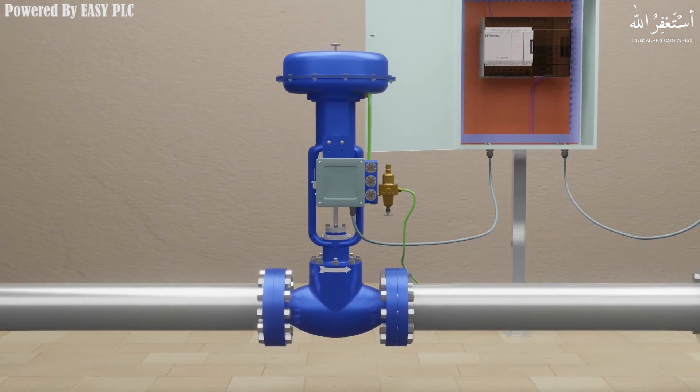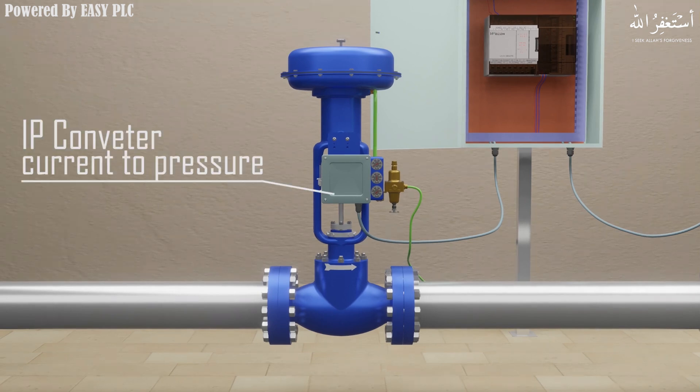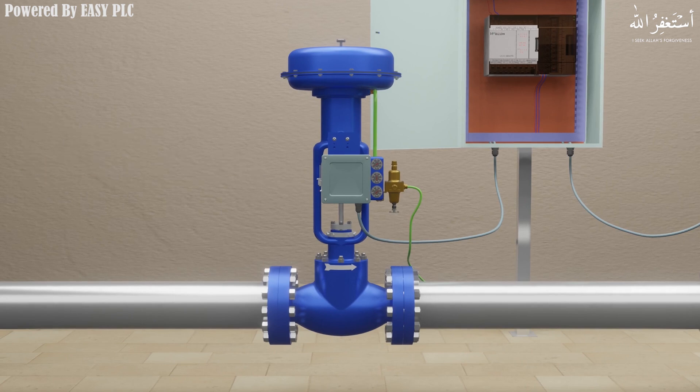Because the PLC signal is electrical, most common signal type is 4 to 20 milliampere, the control valve may require a device to convert that electrical signal into a pneumatic force so that it can operate. An IP converter, which is a current to pressure converter, will convert electrical signal into pneumatic force.